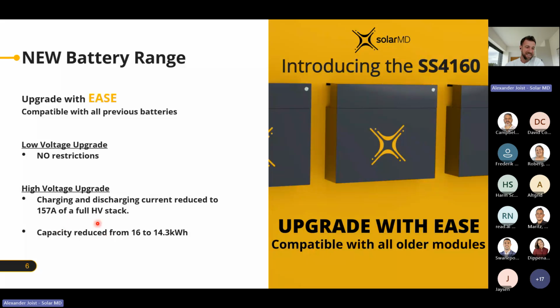157 amps per stack, so it will be reduced from 200. The capacity of this one module will be reduced to 14.3 kilowatt hours from 16, because now we're having a whole stack with 10 to 12 modules in series, and like PV panels, the weakest link decides the whole voltage and output power. So we just need to be aware it will be reduced, but the new battery is a little bit cheaper, so it's not a loss for the client to have a new battery that's 16 kilowatt hours but only provides 14.3. It won't really affect his buying decision, because the new module is anyway a little bit cheaper.